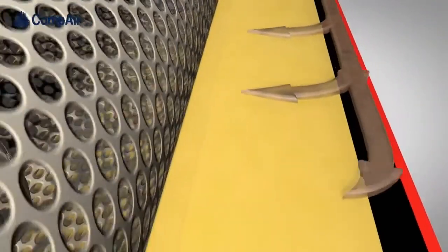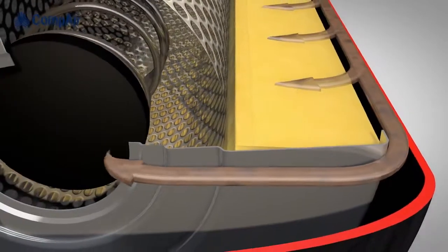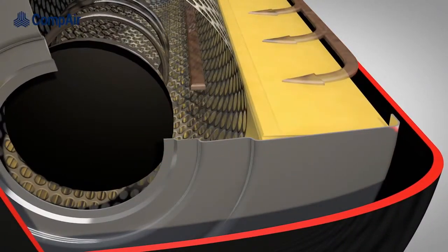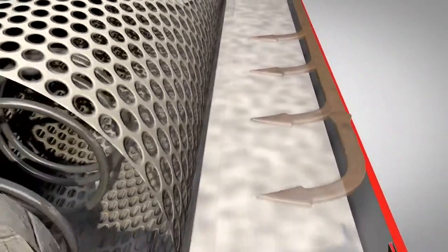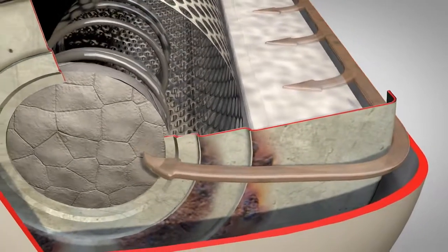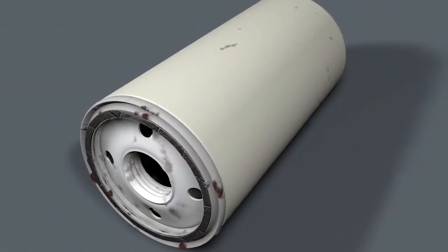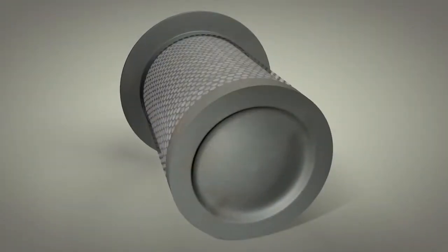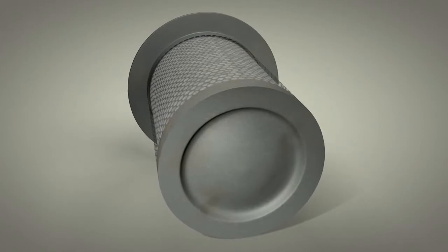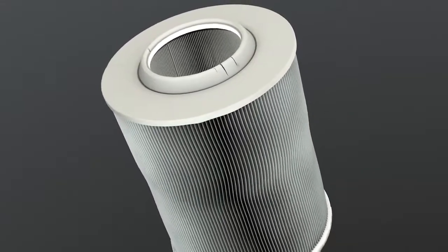The bypass valve has an important function. During a cold start, it ensures that the compressor is reliably lubricated at all times. If it opens too late, the supply of oil to the screw may be inadequate. In this case, the result is undue wear of the screw. To summarize, non-genuine filters are the wrong way to save money because the increased wear or even the failure of the compressor can end up causing considerable expense.